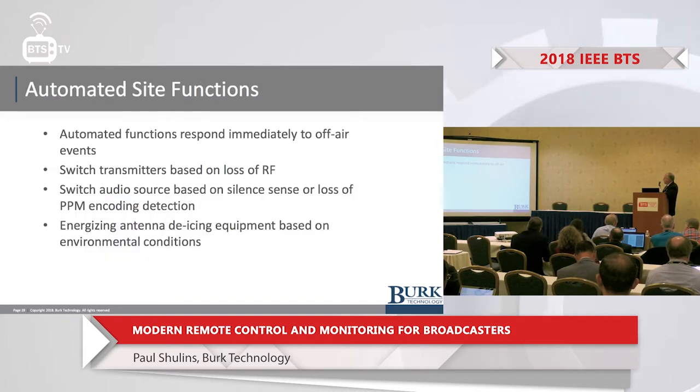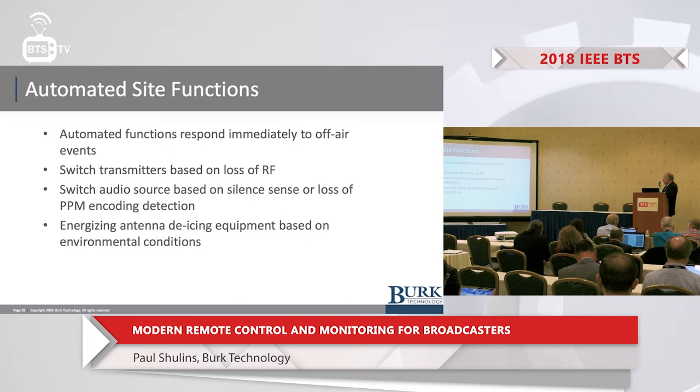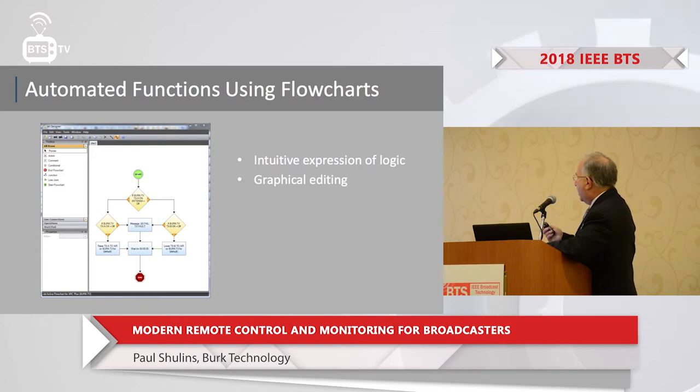Automated site functions respond immediately to off-air events. Remote controls can switch alternate transmitters on the air when they detect a failure with RF forward power output. You can switch audio sources based on the loss of silence sense or the loss of PPM encoding. You can energize de-icing equipment based on environmental conditions such as dew point and temperature getting too close together. Many remote control companies have come up with easy graphical ways to flow chart these situations — you can drag and drop symbols, and when saved into the remote control, these automated functions occur automatically.